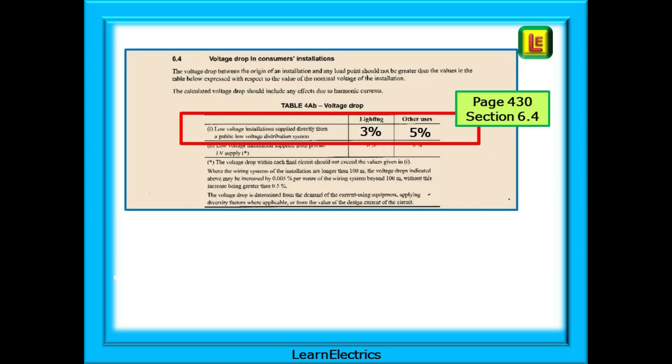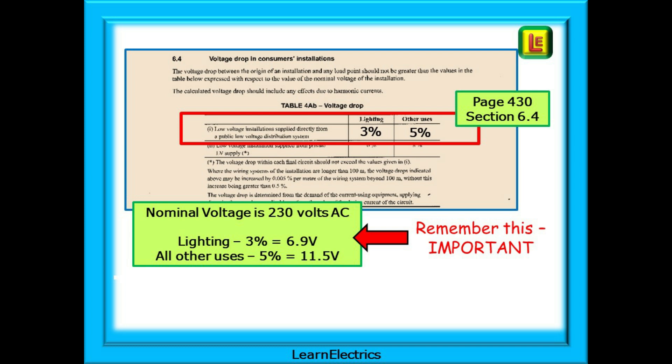This is section 6.4 voltage drop in consumer installations. This table can also be quickly located by looking in table of tables at the back of the book. Right now we're interested in the top row of the table. Low voltage installations supplied directly from a public low voltage distribution system. In other words the national grid. This table tells us that the maximum permissible voltage drop should not be greater than 3% of the nominal voltage for a lighting circuit and not more than 5% for all other circuits. Shown here are the voltage limits that 3% and 5% represent for a single phase nominal voltage of 230 volts. This means that lighting has a voltage drop limit of 6.9 volts and all other uses has a limit of 11.5 volts. This table is often used for exam questions. Learn how to find it.